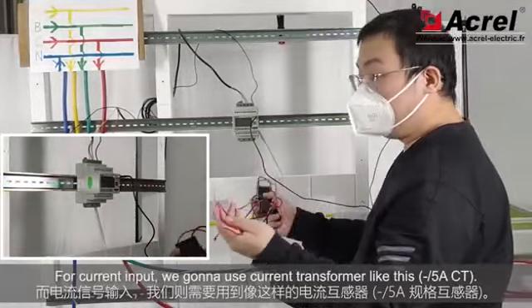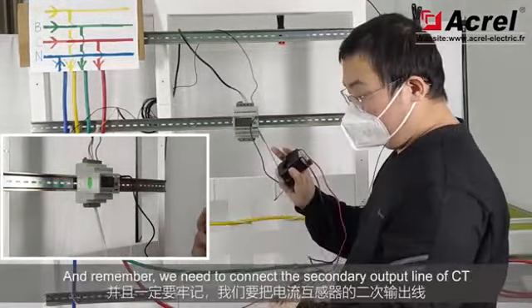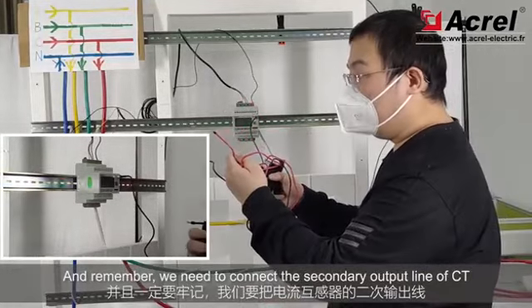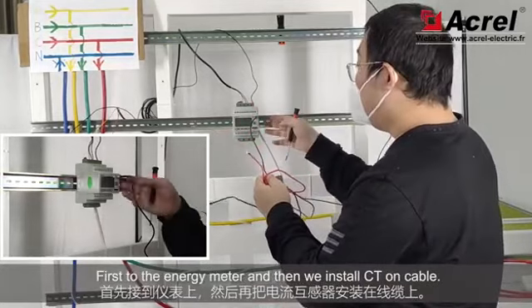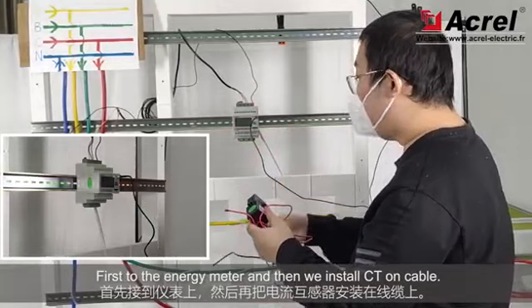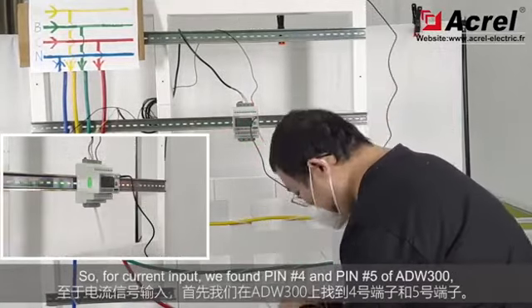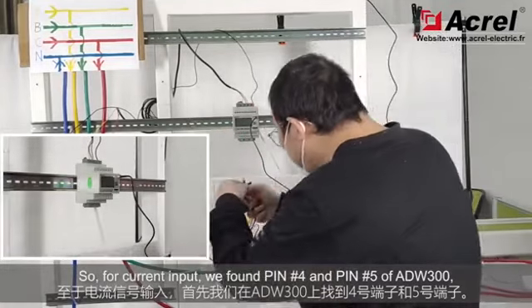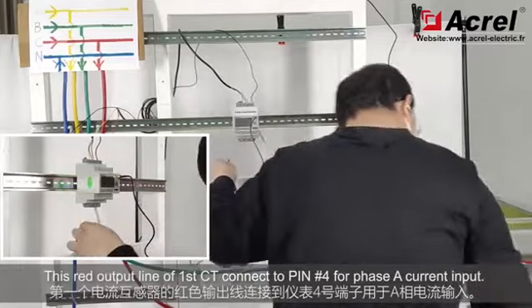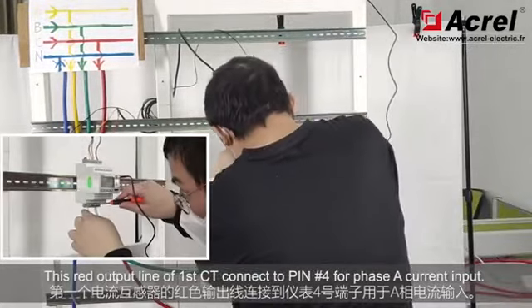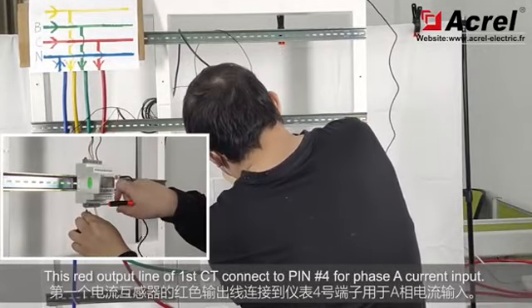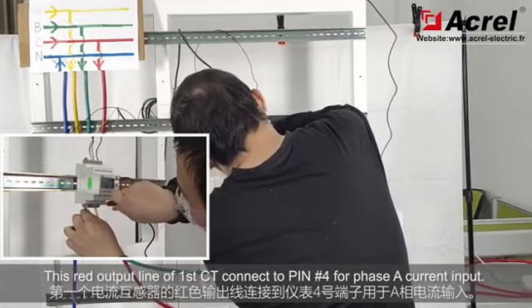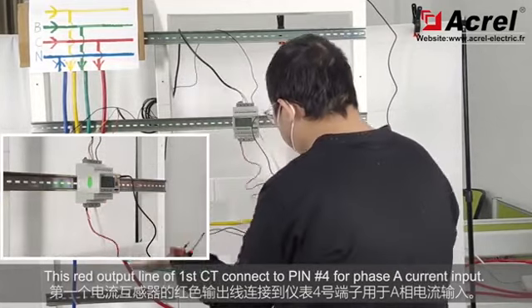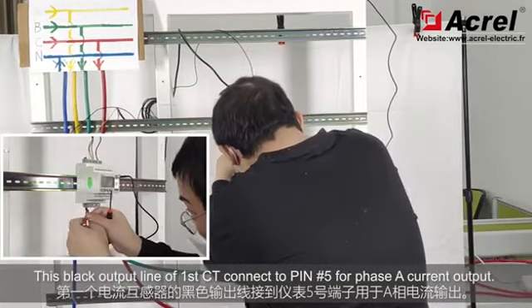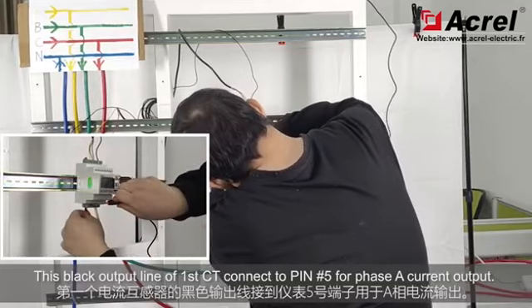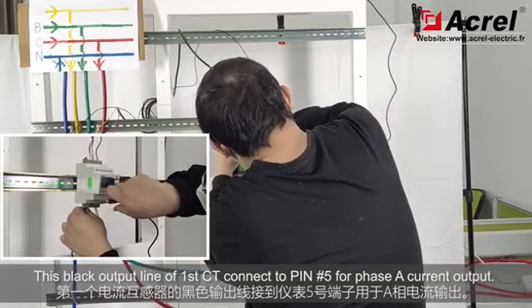For current input, we're gonna use current transformer like this. And remember, we need to connect the second output line of CT first to the energymeter, and then we install the CT on cable. This can't be reversed. So for current input, we found pin 4 and pin 5. This red output line connect to pin 4 for phase A current input, and this black output cable connect to pin 5 for phase A current output.